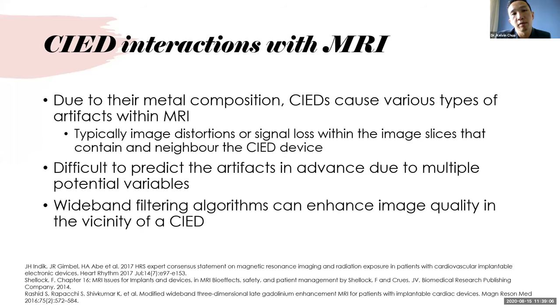So what about the other way - the device interactions with MRI? The device, on the flip side, can also interact with the MRI to cause image distortion. Due to the metal composition, devices and leads can alter the local magnetic field, which causes misreading of the correct localization of the proton signal by the MR scanner.